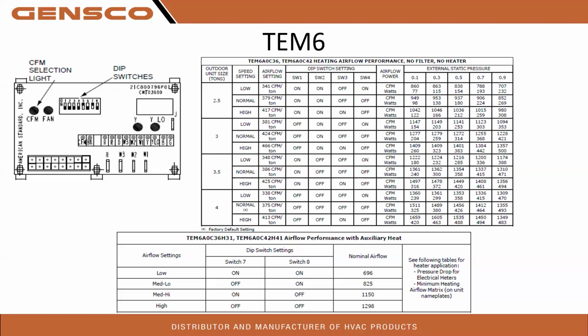Thanks. Thank you, Mark. Again, Mark has years of experience and he's pointing that out. It's bringing attention: higher amperage, higher wattage will lead to premature failure, right? So these ECM motors will keep that CFM, but your wattage goes up. What costs money to operate? Your watts. You pay per watt. So higher static pressure means a costlier electric bill because you're using more wattage. So that is something to check out too.